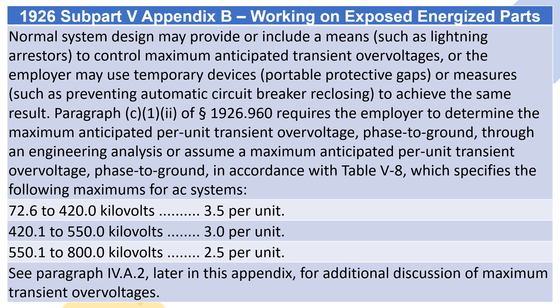Paragraph C.1.2 of Section 1926.960 requires the employer to determine the maximum anticipated per unit transient overvoltage, phase-to-ground, through an engineering analysis, or assume a maximum anticipated per unit transient overvoltage, phase-to-ground, in accordance with Table V-8, which specifies the following maximums for AC systems: 72.6 to 420.0 kilovolts — 3.5 per unit; 420.1 to 550.0 kilovolts — 3.0 per unit; 550.1 to 800.0 kilovolts — 2.5 per unit. See paragraph IV.A.2 later in this appendix for additional discussion of maximum transient overvoltages.